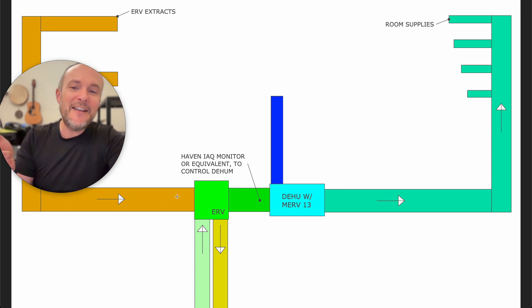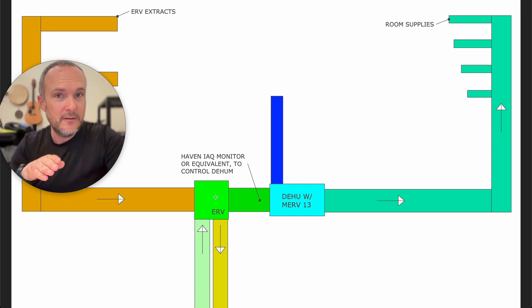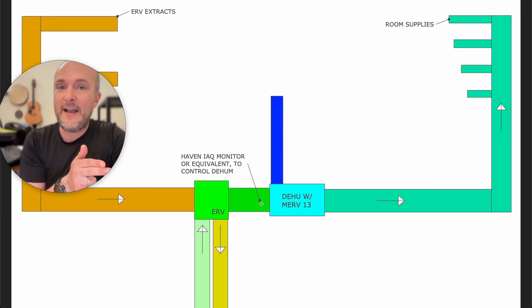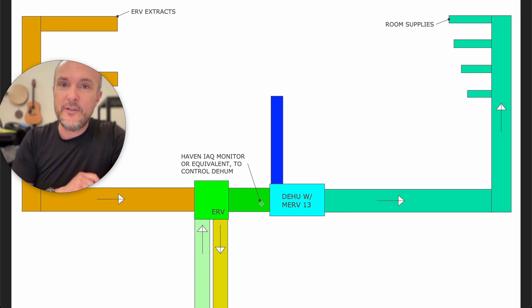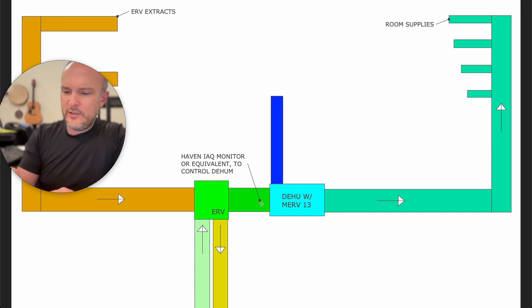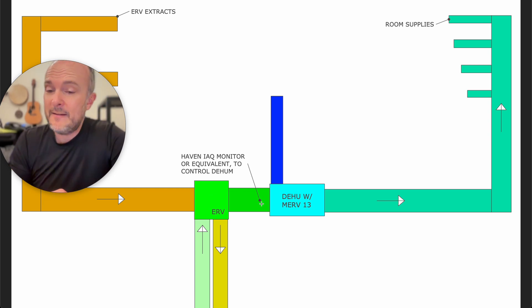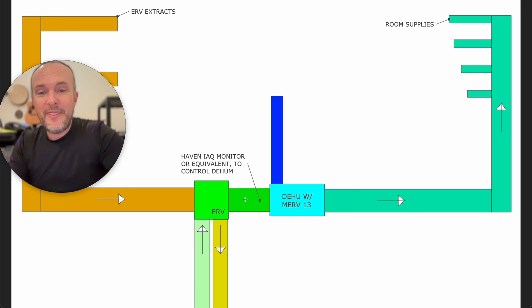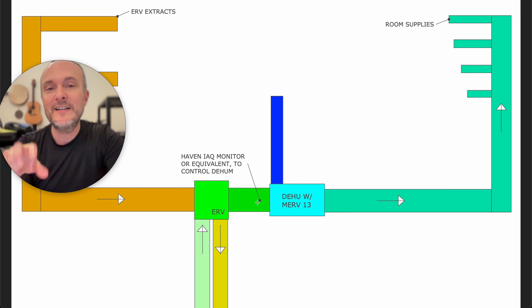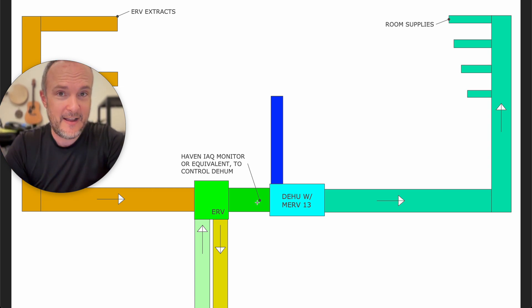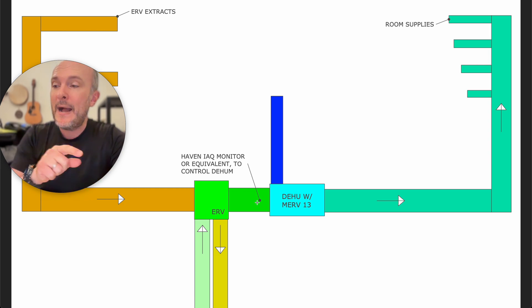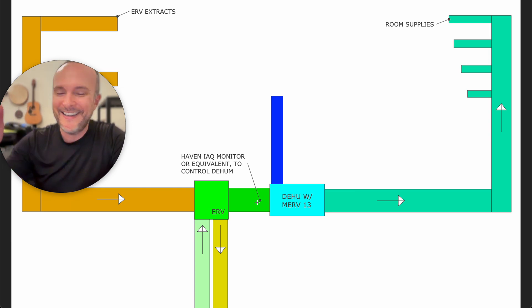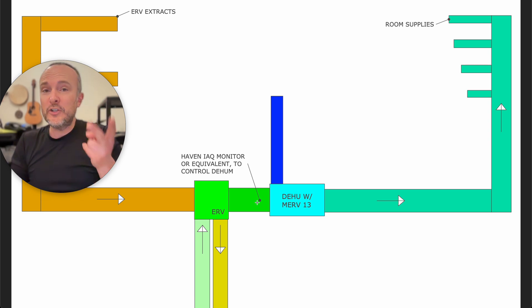So number one, let's imagine it comes in 95 degrees, 40% relative humidity. It hits this ERV core, and that is going to take some of the temperature edge off and some of the humidity edge off. Let's say it goes through and it's 85 degrees but still 40% relative humidity. That's still way too humid for your house because even at 85 degrees, we're looking at 85, 40—at 75 degrees that's 63% relative humidity. Again, you need to dry that out. But the sensor here is going to say, 'Oh, this air is 85 degrees, 40% relative humidity.' It doesn't even care about the 85. It's just going to take the 40 and it's going to say, 'Great, 40 percent. My set point is 50. I only start drying when it gets over 50.' So that's number one: it's not going to know that it needs to dry this air.